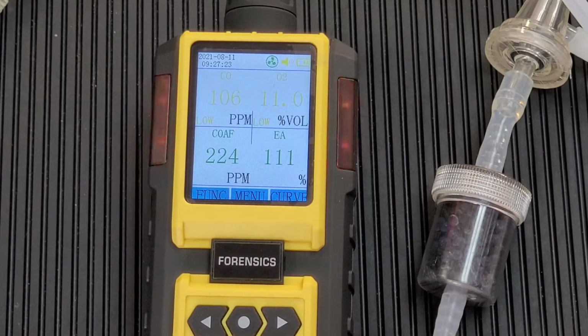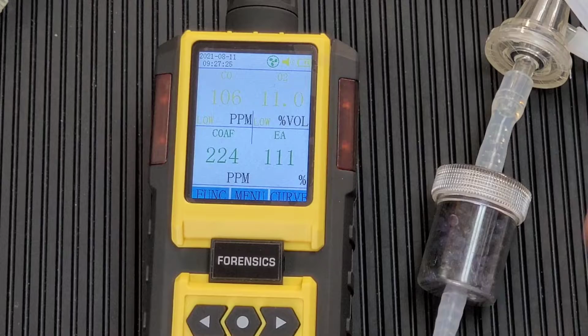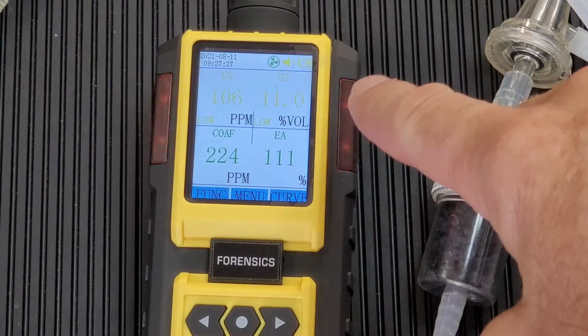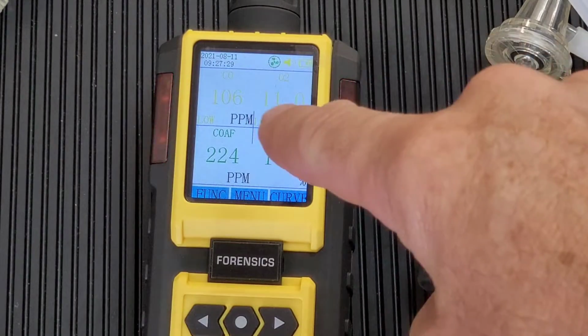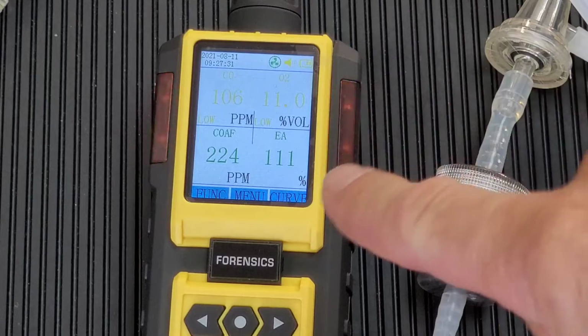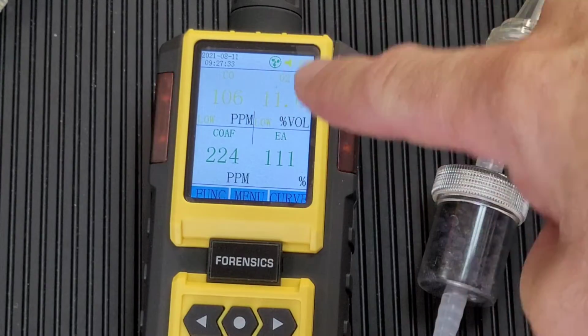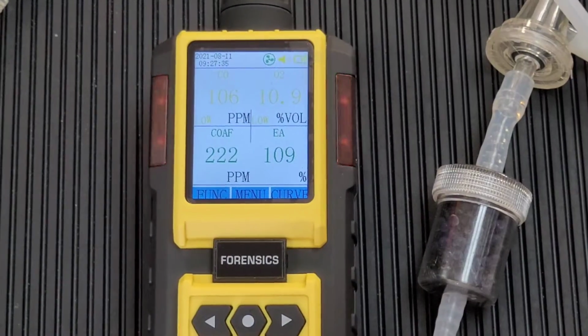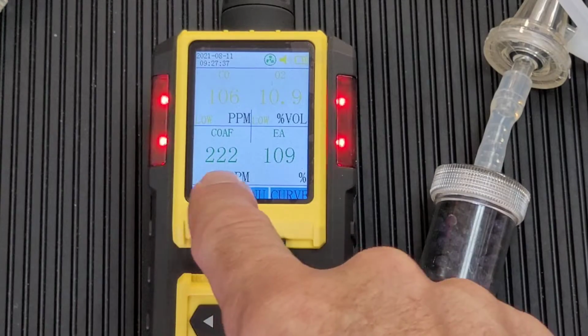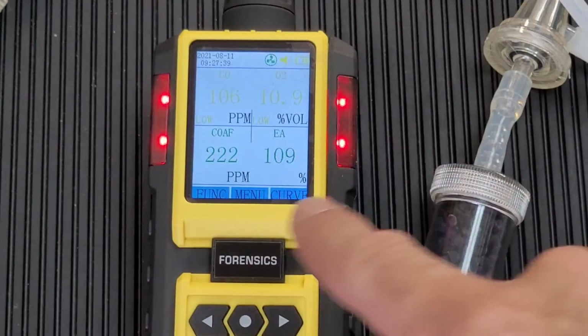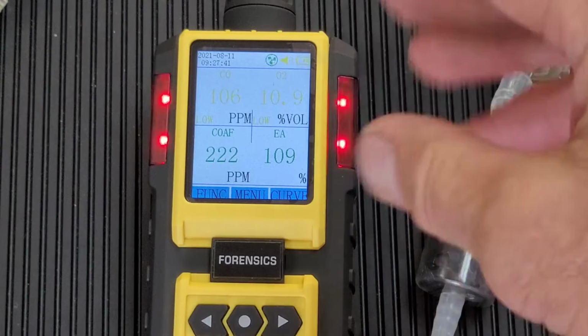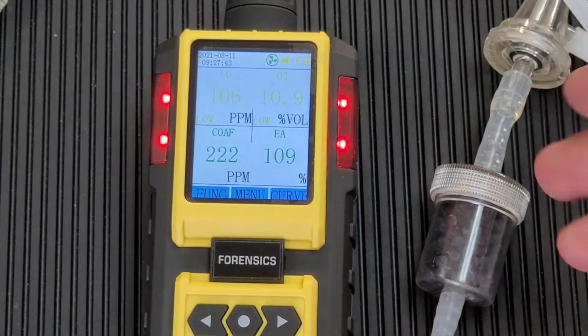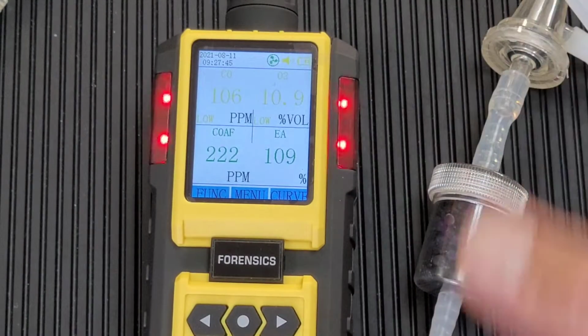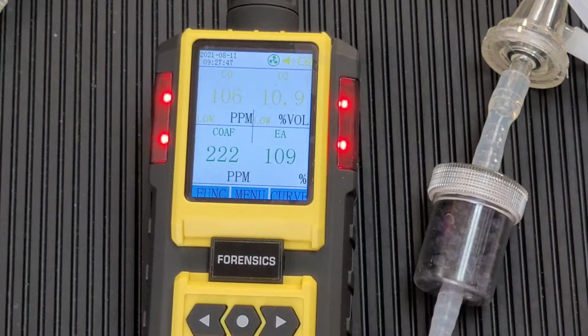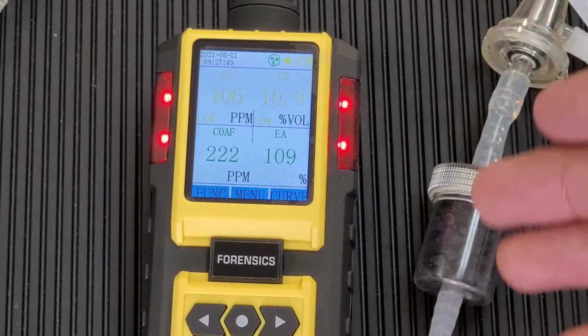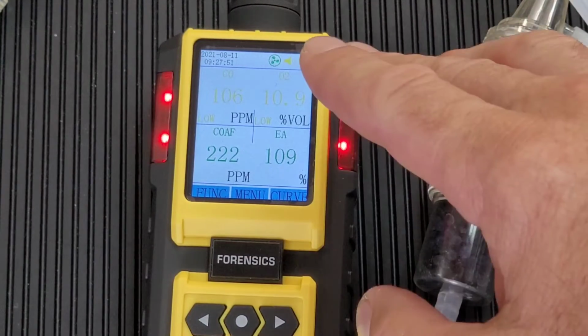All right, folks, we're back. It's been about a good minute, and as we could see, we have oxygen 11% and going down. Carbon monoxide on the mark, 106 is in the bottle, and we're getting 106, 107 on the analyzer, folks. COAF is calculated, and so is EA. Again, all on one screen. Dr. Coz loves everything on one screen, folks. That's what we have, within specifications, within reasonableness of a combustion analysis. Nothing out of the ordinary.